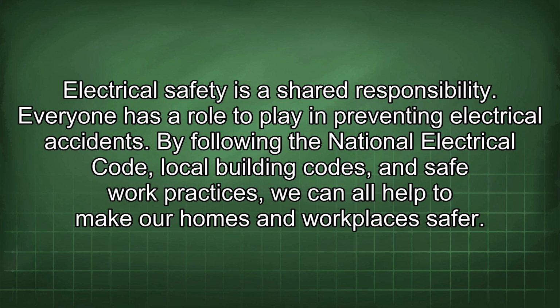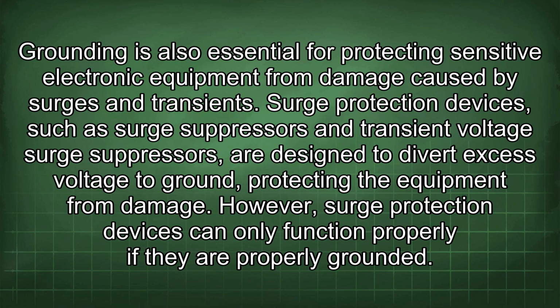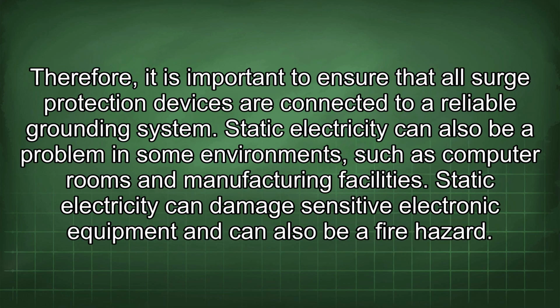Grounding is also essential for protecting sensitive electronic equipment from damage caused by surges and transients. Surge protection devices, such as surge suppressors and transient voltage surge suppressors, are designed to divert excess voltage to ground, protecting the equipment from damage. However, surge protection devices can only function properly if they are properly grounded. Therefore, it is important to ensure that all surge protection devices are connected to a reliable grounding system.